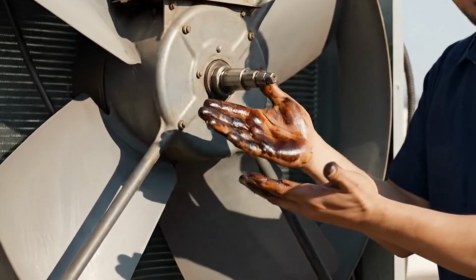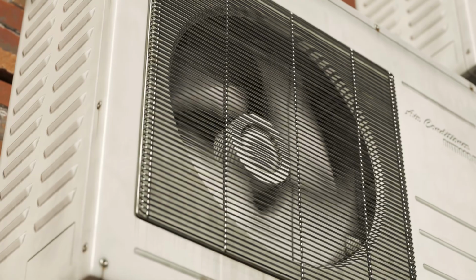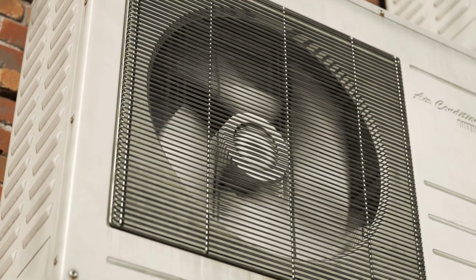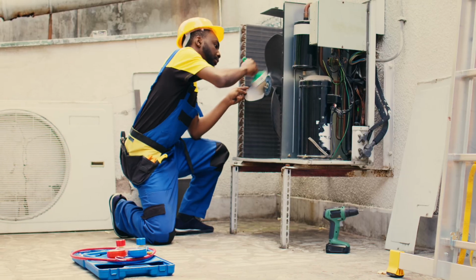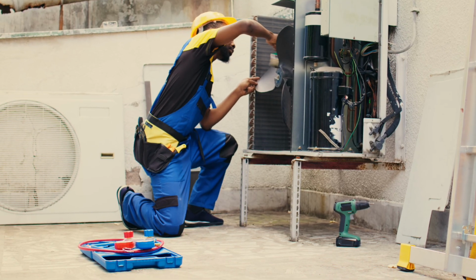If there's no oil on the compressor, if you reach in underneath the fan motor and there's oil on your hands, another sign the bearings are leaking. That is going to be a mechanical noise you're going to hear from your condenser fan motor. Another noise you could hear could be caused by an unbalanced fan blade. Fan blades can get damaged, can get bent, can get dirt accumulating on them that tend to get them out of balance. That will continue to worsen and wreak havoc. And that's why you need to have your system maintained and cleaned.